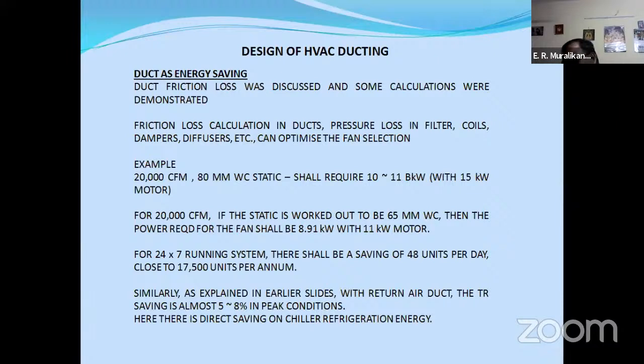These examples I am not correlating for ductable units. These are package units, ductable units, which have a very low static of maybe 30 or like that, and it can throw up to 80 feet or so distance. So ductable package units I am not talking of, because they're factory assembled and they have a different mechanism. This ducting is mainly for centralized air handling units which have supply duct and return duct. The importance of return duct I already explained. So we should make it a point to bring everything into practice.